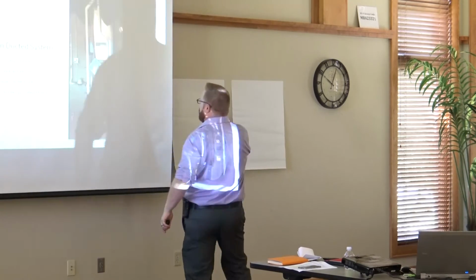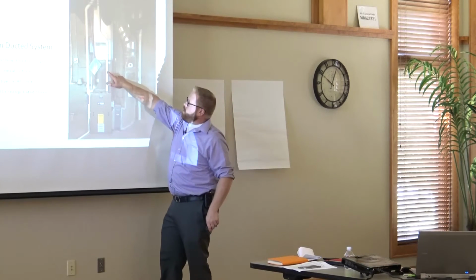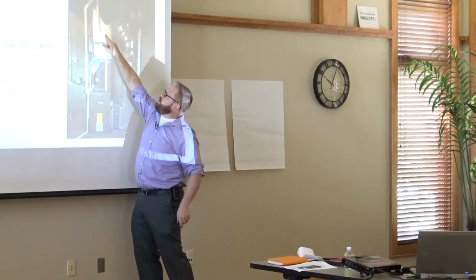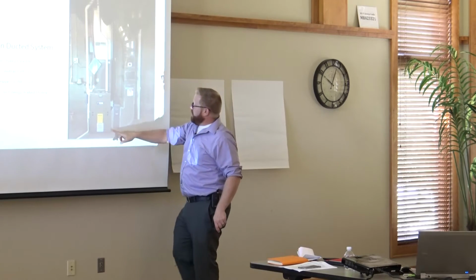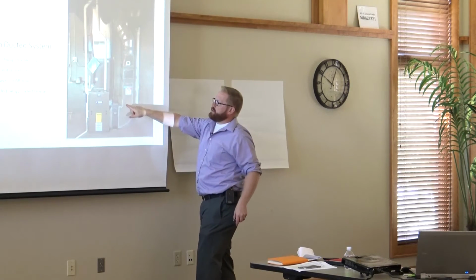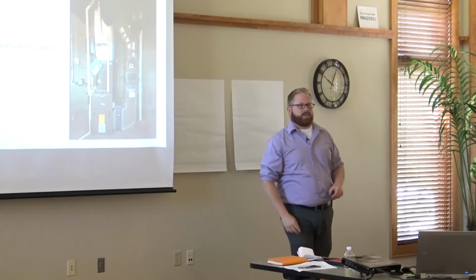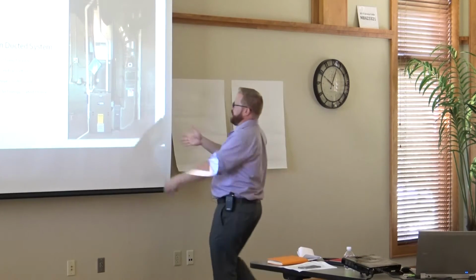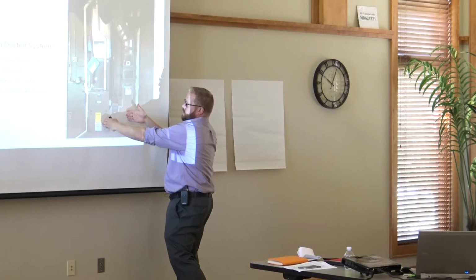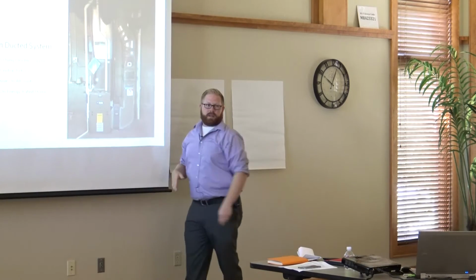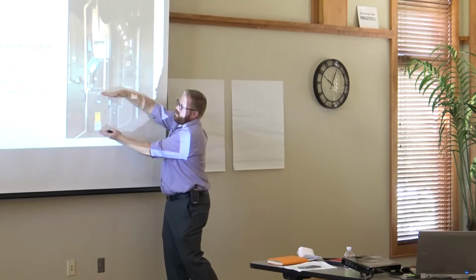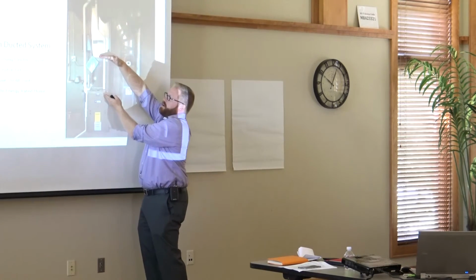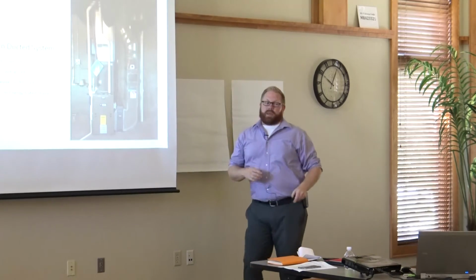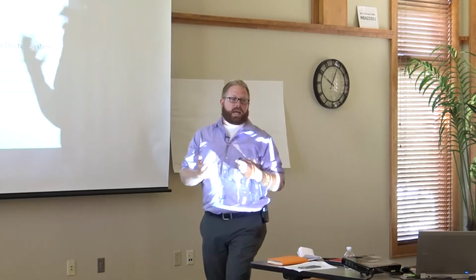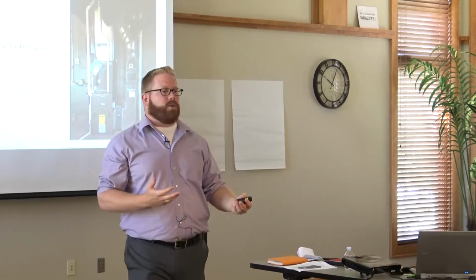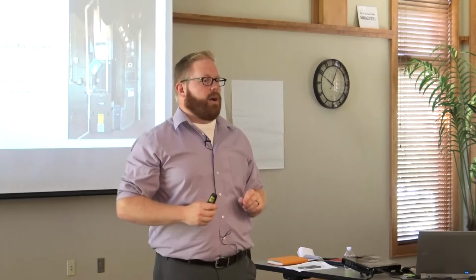It's kind of hard to see, but there's a little hole here in our exhaust pipe, a hole up here, a hole in the cabinet, and a hole in the return on this side. So we're checking static pressures across our entire system - what it is across our filter, our furnace, our air conditioning coil. That way we can ensure our duct system is sized appropriately, and we're setting up the airflows appropriately based on that house.